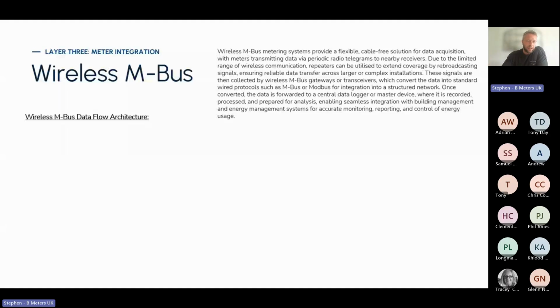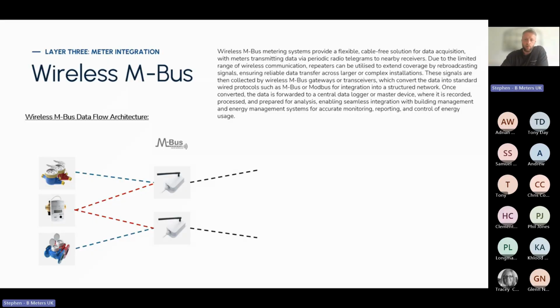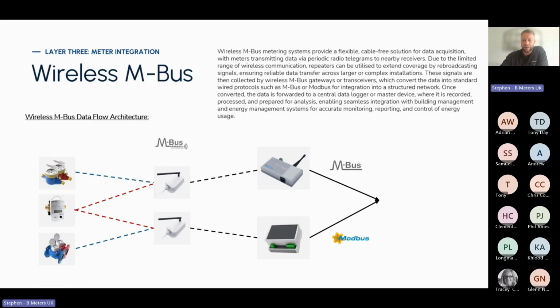So I just wanted to go through the wireless M-Bus data flow architecture. First, you have your meters. They send out wireless M-Bus payloads. Then you include wireless M-Bus repeaters. Wireless M-Bus repeaters will then send data on. In this case, I've got a wireless M-Bus to wired M-Bus gateway, or a wireless M-Bus to Modbus gateway. So this then wires directly into a device such as the EMU M-Center or the Elvaco or any other that you prefer to work with and to integrate with.